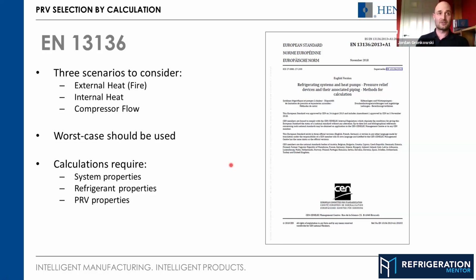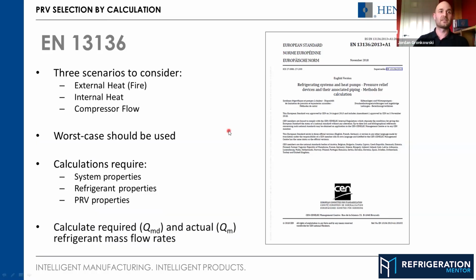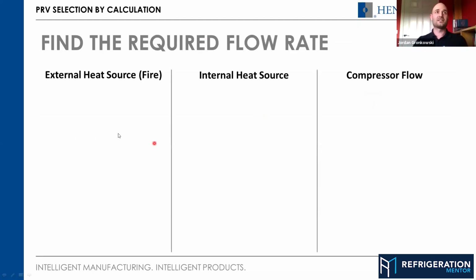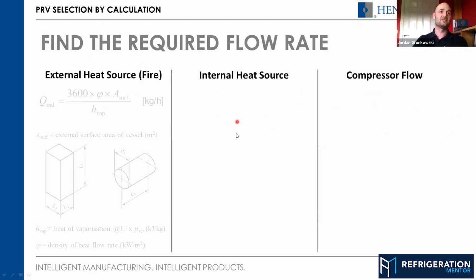They require system properties, refrigerant properties, and PRV properties, obviously, as well. And basically, you're looking at 2 terms. You're calculating a required flow rate, the QMD, as it's called. This is what's required to keep the system safe in these scenarios. And you're then calculating QM, which is the actual rated flow rate of the valve. And effectively, you make sure the valve has more rated flow than your requirement. So finding the required flow rate is the first step. As I mentioned, you've got your 3 scenarios here: external, internal, compressor.